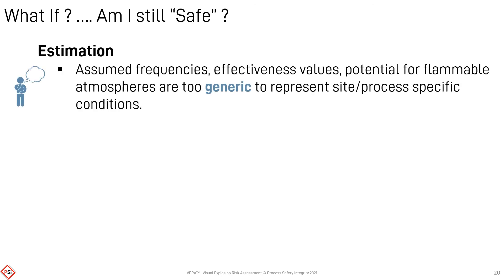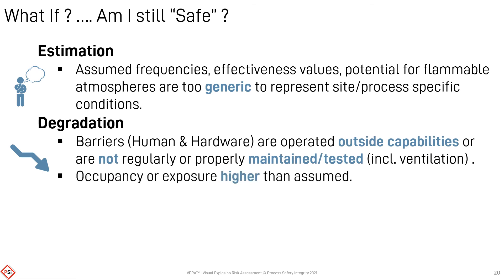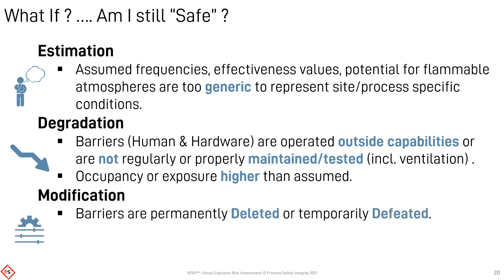Qualifying or quantifying the components allows sensitivity analysis of the assessment to be conducted — for example, how does the risk change if I change this category or value? Similarly, what is my current risk because my barrier effectiveness has decreased, or my occupancy has increased, since the previous or original assessment? Representing the fire or explosion scenario visually provides context and highlights the criticality of barriers, so that the impact of any planned or unplanned changes to them can be properly evaluated.